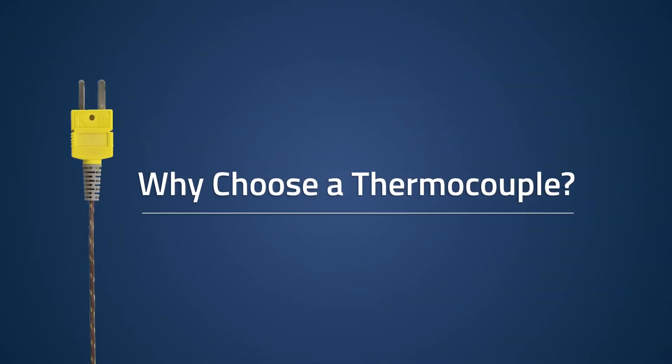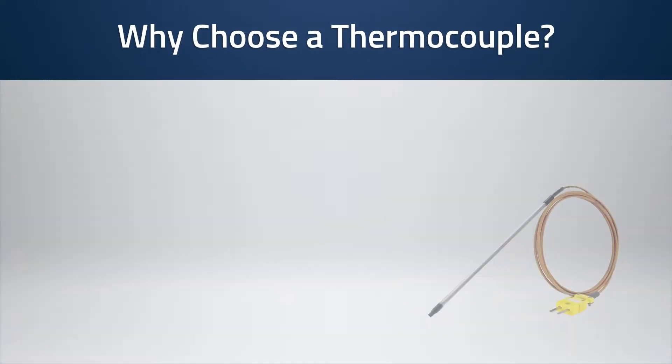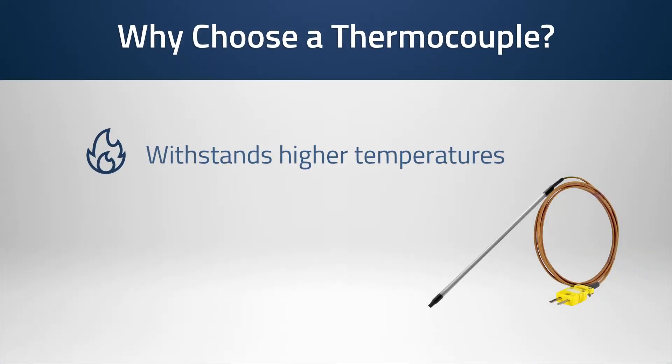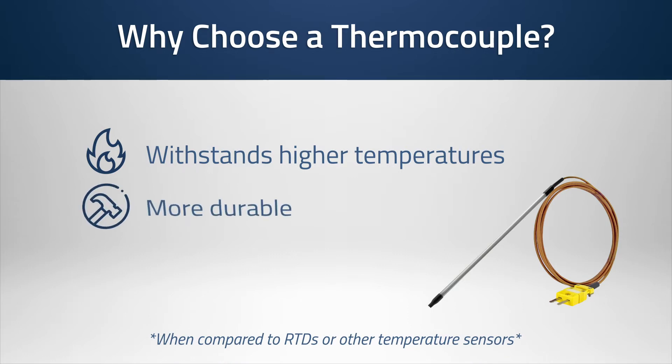Some reasons to choose a thermocouple as opposed to an RTD or other similar probes include: many thermocouples can withstand much higher temperature ranges when compared to alternative options. Thermocouples are also considered to be more durable than other measurement options, and in general, the average thermocouple is two to three times less expensive than an RTD.